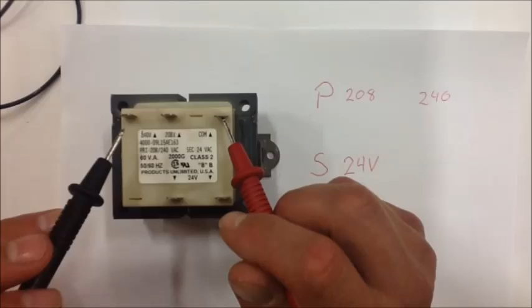So again, I'm going to give you a little indication of how this transformer works. I've got my meter again. I'm going to set my meter to continuity, so we're testing for a complete path again. Anytime I have a transformer, I should always have a good secondary winding, and I should have a good primary winding.